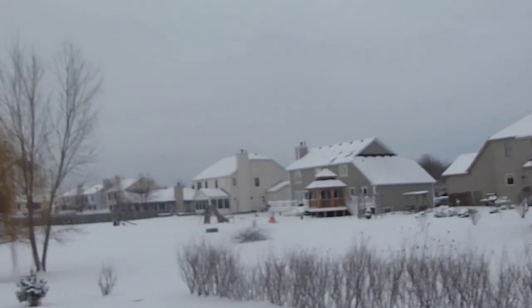Here's the York air conditioner. Here are the numbers: 3 ton, 2001. 036 means 3 ton. All those homes have Yorks with 80% efficiency gas furnaces — all straight cool units with gas furnaces.